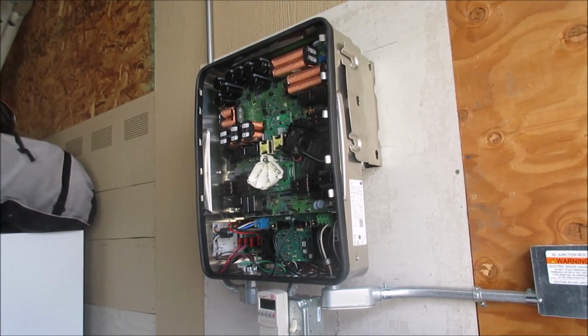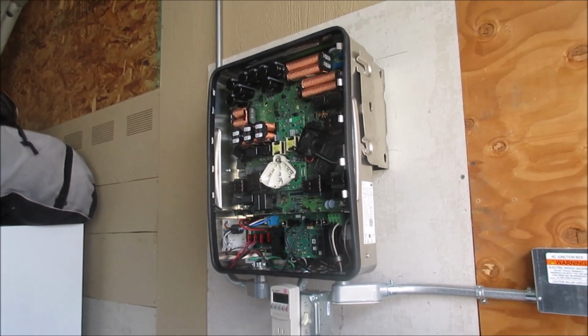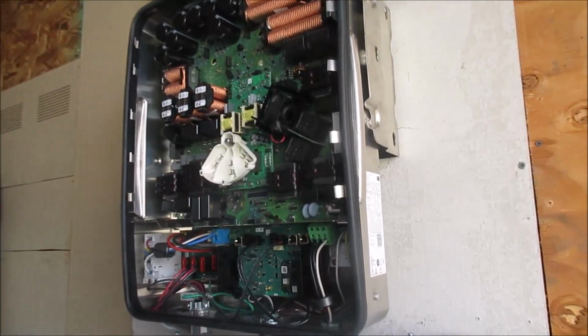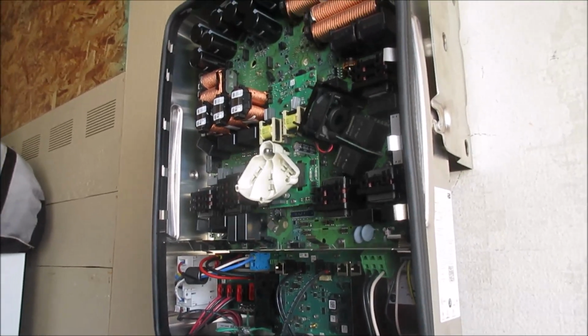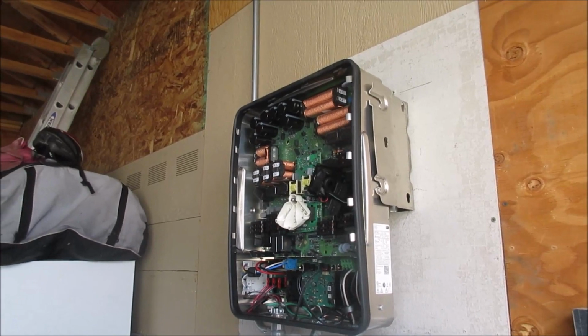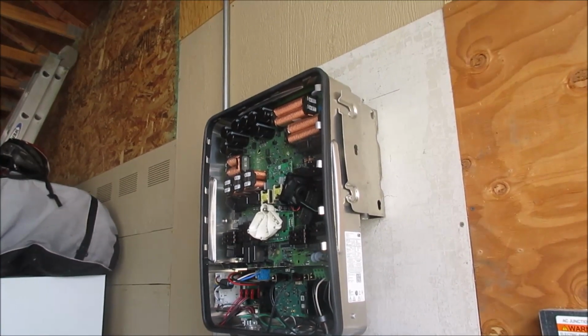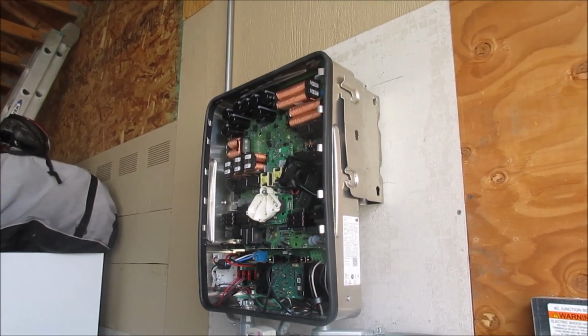Yeah, I need to commission it, but I have to go through an app, and that's going to take me a few minutes. Okay, so you have to set up an app. Yeah. And then, the previous test was just to make sure that all the panels were contributing to the DC potential coming off the roof, and because they have a shutdown monitor on them and there's no load, they were only delivering about 0.5, 0.6 volts DC, right? Yeah, about 0.6. And so all 10 of them were delivering about 6 volts DC.